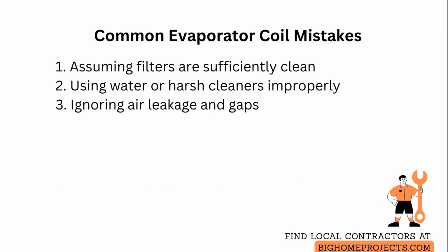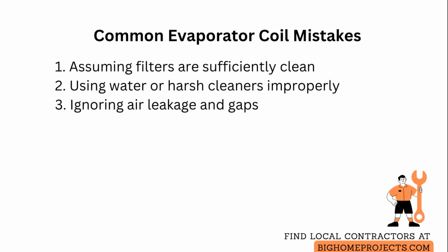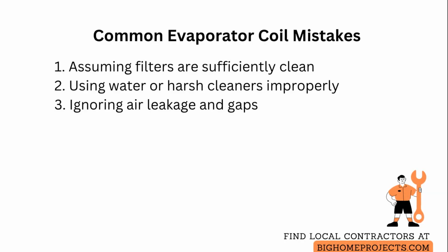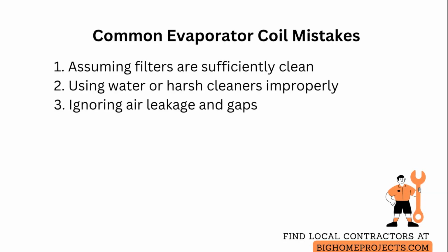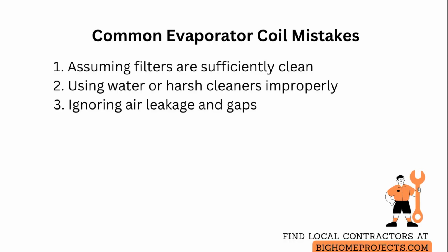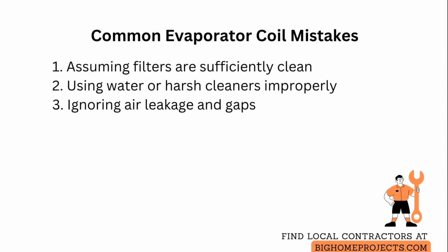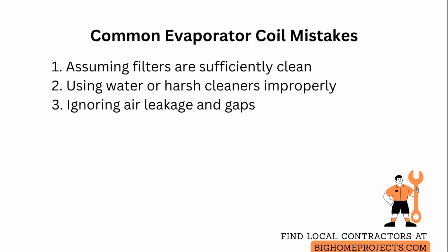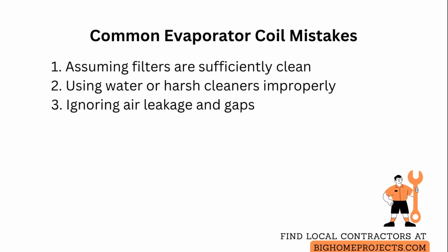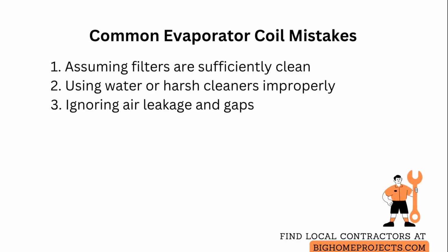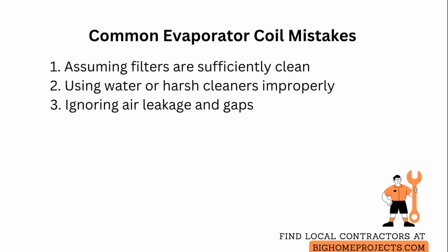Common mistakes include assuming a clean-looking filter is sufficient when it is not. Filters can appear clean on the surface but be loaded internally, so change or clean them on a strict schedule. Another mistake is using water or harsh cleaners on the coil without power isolation and proper runoff control. Always power down and block runoff from entering electrical areas or ductwork.